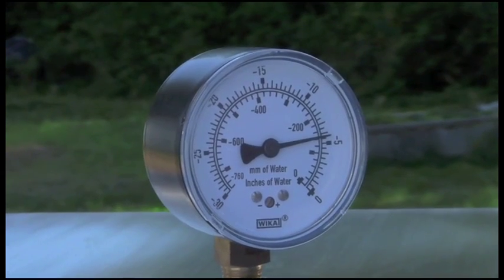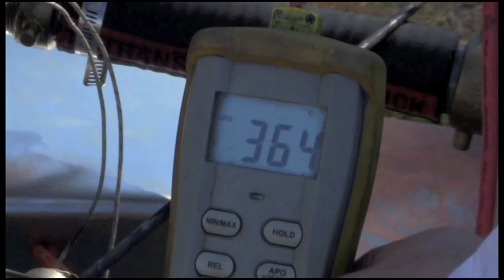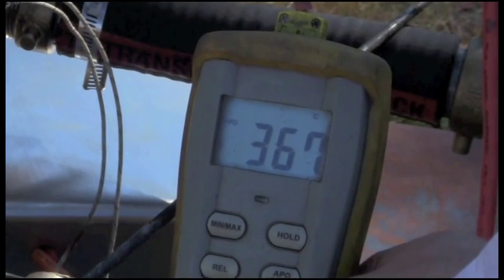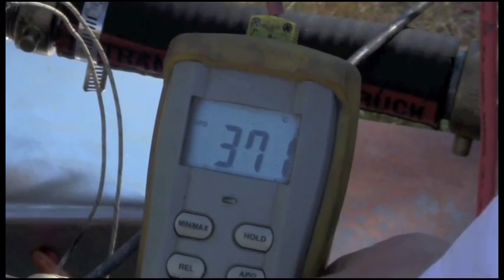Pressure drop on startup is about 6. Our gas outlet temperature is about 370 degrees centigrade before going to high temperature filtering, and coming out of the filter we're about 150 degrees centigrade. Gas exit temperature is about 80 degrees Fahrenheit, and the particulate sample was 9 parts per million in the 8th hour.